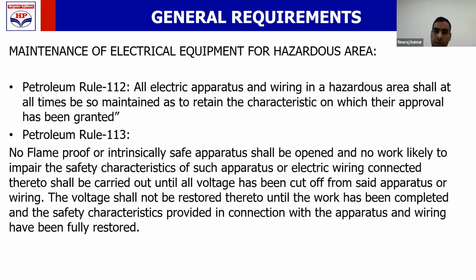Now, how to do the maintenance in those electrical equipment installed in the hazardous area? If you are doing maintenance on those electrical equipment, they must be in the de-energized condition. You are not supposed to open explosion protection electrical equipment in a hazardous area in the energized condition. They must be de-energized. If you are using a flame or a spark source for doing maintenance, then you should comply with the requirement of the hot work.